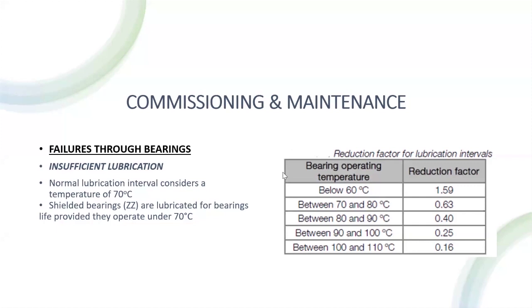So if per the OEM, after 2,000 running hours, you are supposed to grease, ensure you have systems in place that observe the running hours, and after which you are notified by your system that it is due for greasing. Normal lubricant intervals are done based on 70 degrees Celsius. And shielded bearings, the ZZ or RR bearings, are lubricated for the life of the bearing. So that is for a temperature of 70 degrees Celsius.